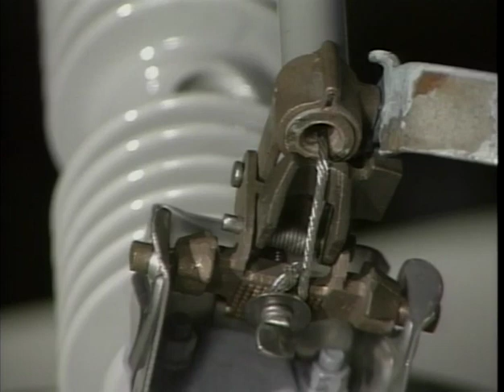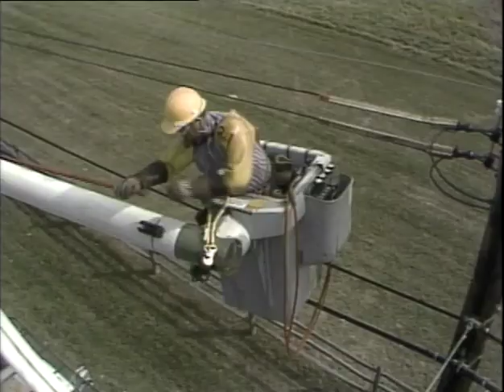A load break disconnect switch can operate under load to de-energize and isolate a circuit. Like the other type of switch, its parts include a disconnect assembly, a switching arm, switching contacts here and here, and a latch. Note that the switching arm in this case is not one solid piece. It contains a cylindrical housing or fuse tube. And inside the fuse tube is a fuse link.